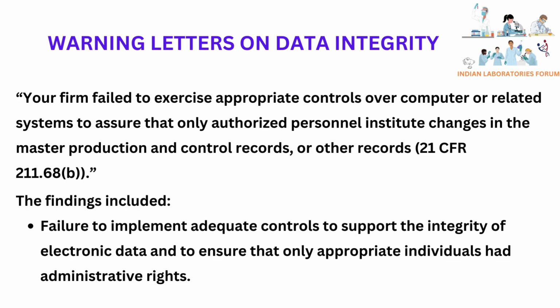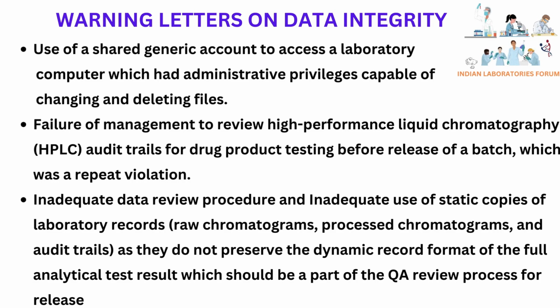The findings included failure to implement adequate controls to support the integrity of electronic data and to ensure that only appropriate individuals had administrative rights. Use of a shared generic account to access a laboratory computer, which had administrative privileges capable of changing and deleting files. Failure of management to review high-performance liquid chromatography (HPLC) audit trails for drug product testing before release of a batch, which was a repeat violation.